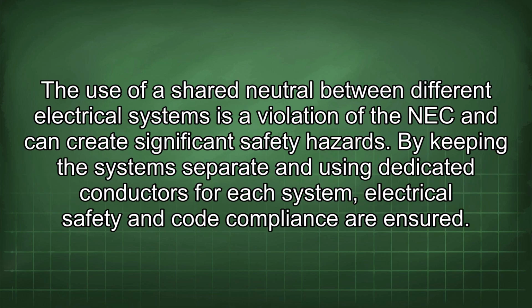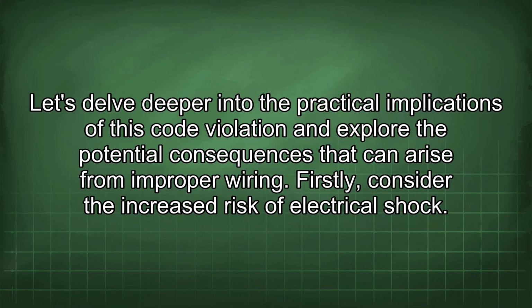The use of a shared neutral between different electrical systems is a violation of the NEC and can create significant safety hazards. By keeping the systems separate and using dedicated conductors for each system, electrical safety and code compliance are ensured. Let's delve deeper into the practical implications of this code violation and explore the potential consequences that can arise from improper wiring. Firstly, consider the increased risk of electrical shock.